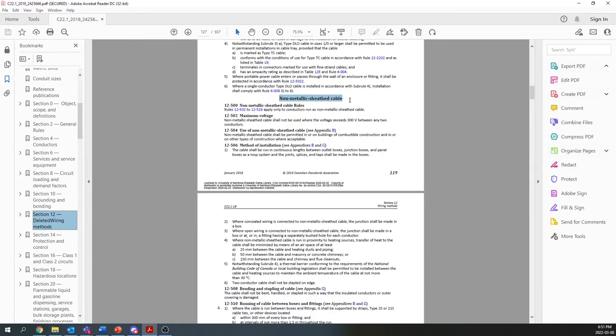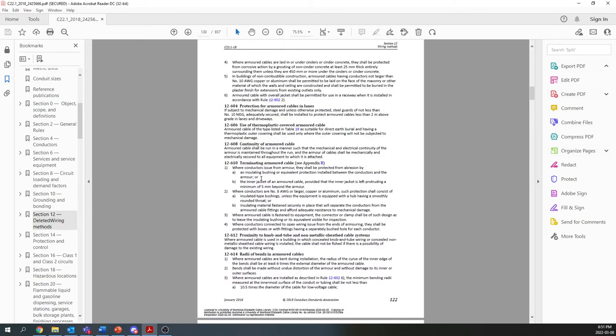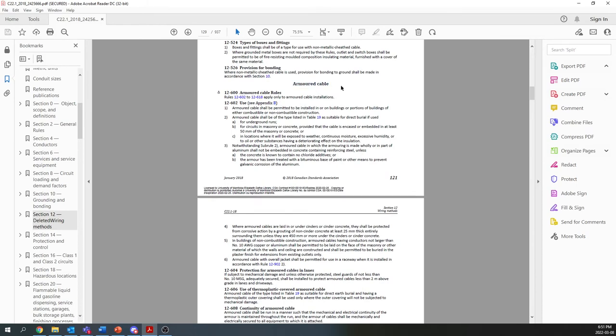Lots of different rules. Non-metallic sheath cable, that is NMD90. That's the kind of white wires you see in your house. Armored cables, you might see in a lot of commercial installations. It's called BX or AC90. It has a kind of wavy aluminum surface. You can get steel armored cables as well, but generally it's aluminum. There's a whole wide range of different types of armored cables that can be obtained with overall plastic jackets, with plastic jackets inside, with different temperature ratings, different purposes, different uses. You can get instrumentation and control cables that are armored and all that sort of stuff. So armored cables are very useful, flexible. You can use them in a lot of different types of situations. Versatile, that's the word I'm thinking of.